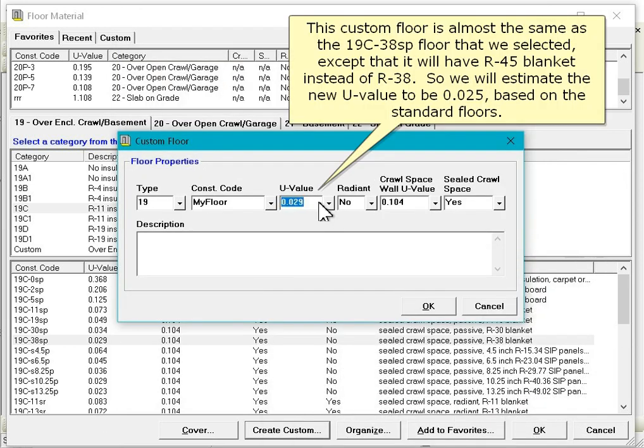The custom floor is almost the same as the 19C-38SP floor that we selected, except that it will have R45 blanket instead of R38. So we will estimate the new U-value to be 0.025 based on the standard floors.